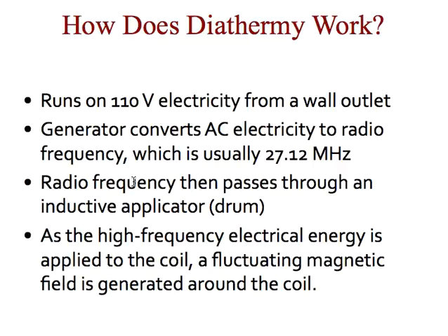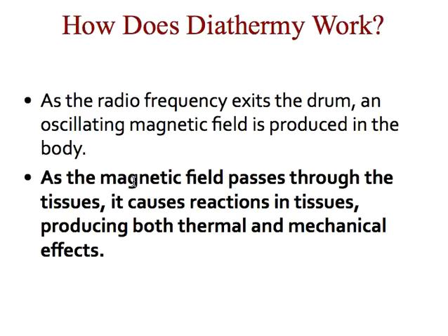How does it work? Pulsed shortwave diathermy runs on 110-volt electricity from the wall outlet. The generator converts that AC electricity into radio frequency — in the case of pulsed shortwave diathermy, that's 27.12 megahertz. The radio frequency then passes through the inductive drum or applicator. As the electrical energy is applied to the coil, a fluctuating magnetic field is generated around the coil. As the radio frequency exits the drum, an oscillating magnetic field is produced in the body. As this magnetic field passes through tissues, it causes reactions producing both a thermal and mechanical effect.